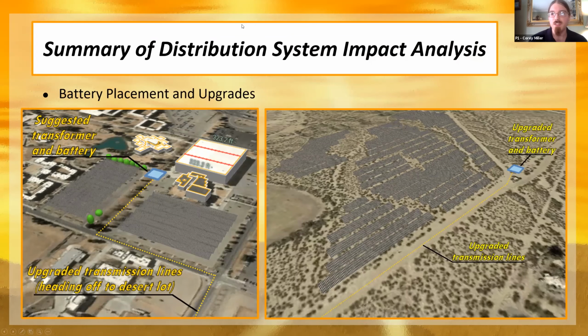So the desert lot by far produces the most energy compared to any of these other sites, so that does impact the distribution system. Based on the increased load on these lines, we are recommending 2 additional transformers at the geothermal substation near the desert lot. These are both 2,500 kilowatt transformers.